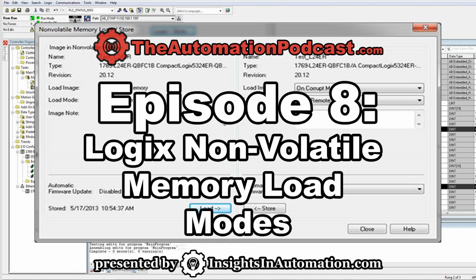In the non-volatile memory tab of the controller properties, we'll press the store button, but this time with the load mode set to on power up. So open controller properties, open the non-volatile memory tab, and where you see load image, change that to on power up. And then go ahead and press the store button again.